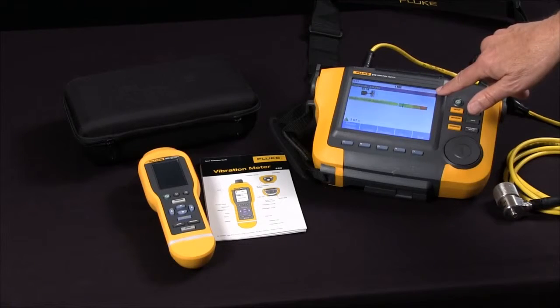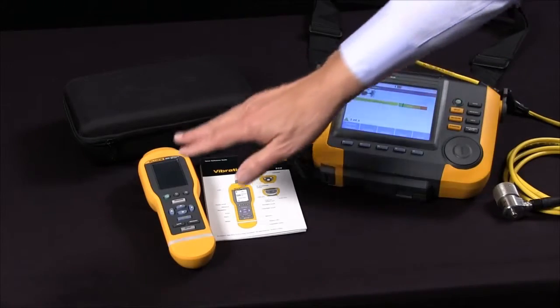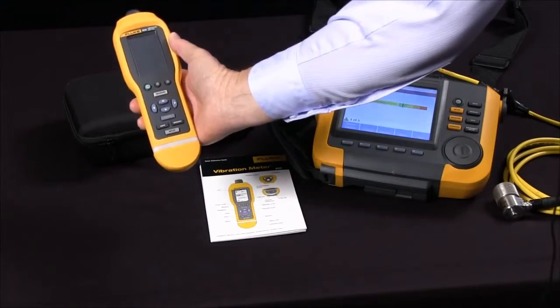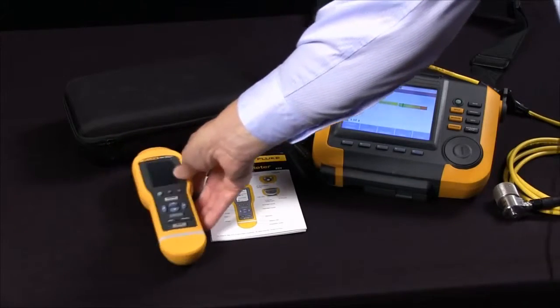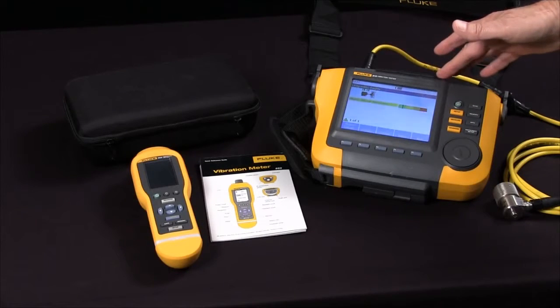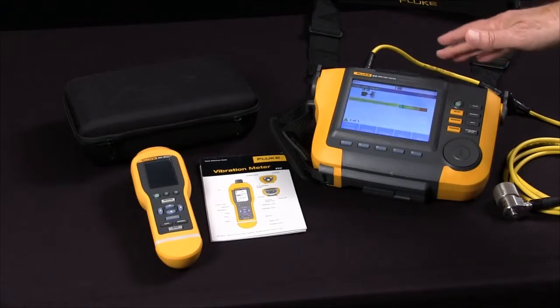So you'd choose the Fluke 805 vibration meter for frontline go-no-go screening of bearings and overall vibration. You choose the 810 for its diagnostic power — the 810 will diagnose the specific fault and location.